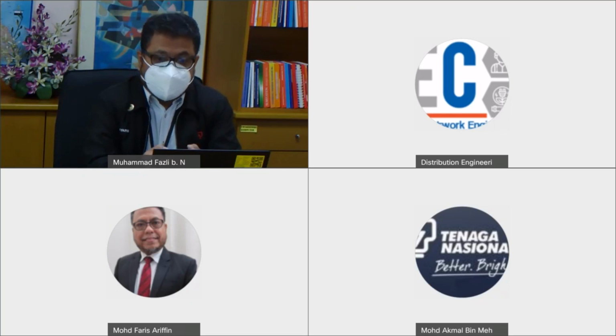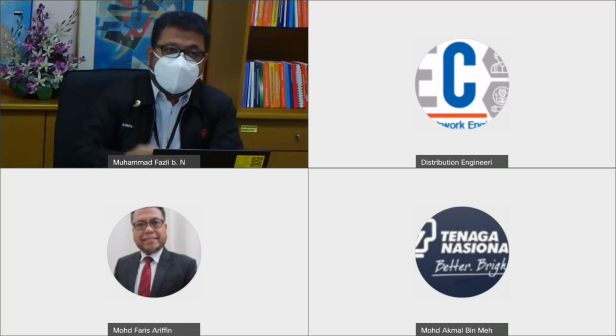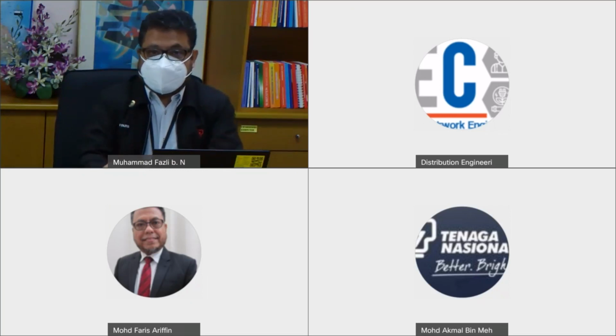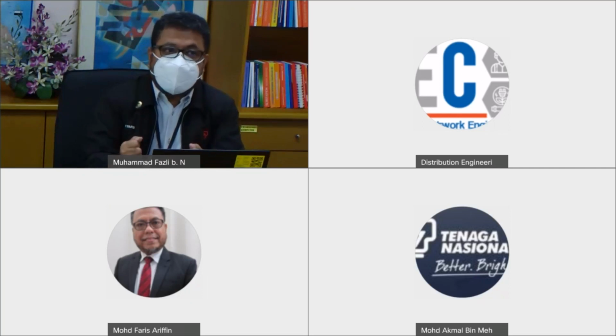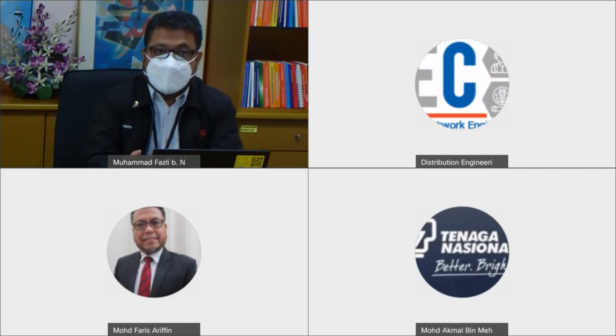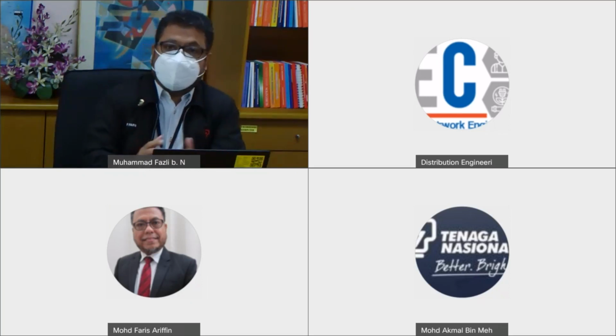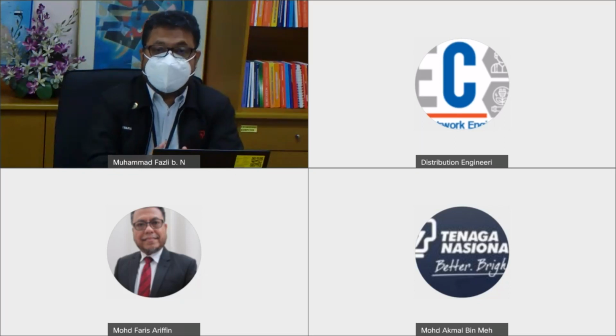So if multiple strikes occur on the line, the surge arrester will have to work overtime. It has to discharge so many times within 1 minute, for example. So it has to have a robust build, and in terms of energy absorption, it needs to be able to absorb and discharge within that 1 minute or 3 minutes.